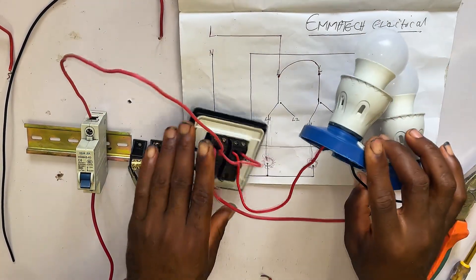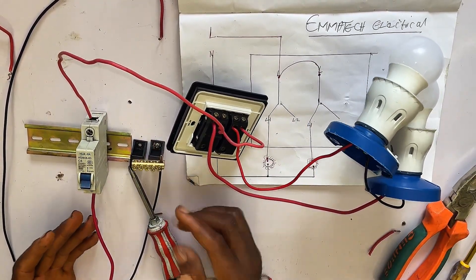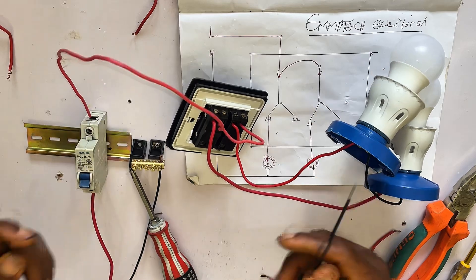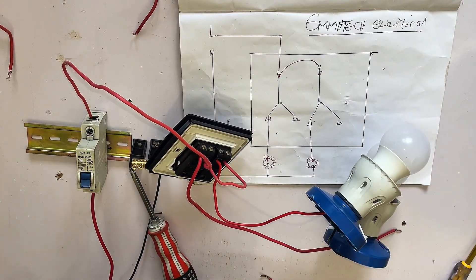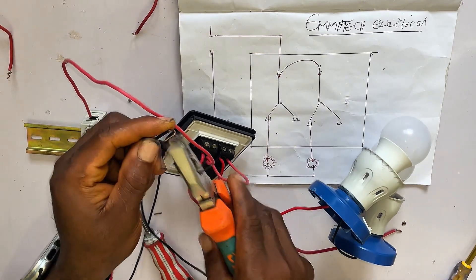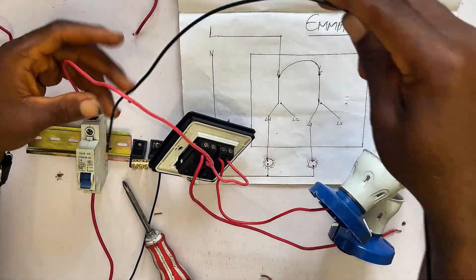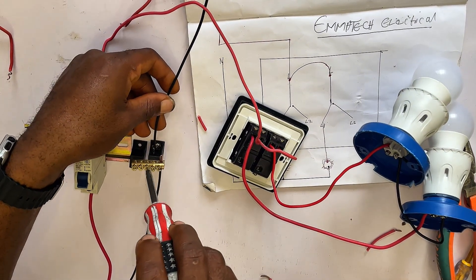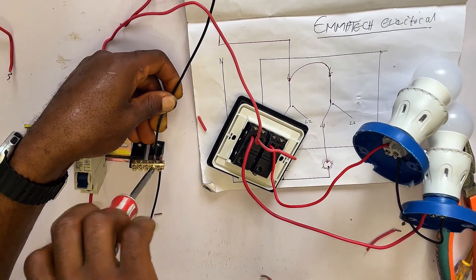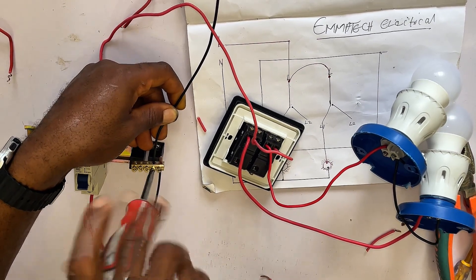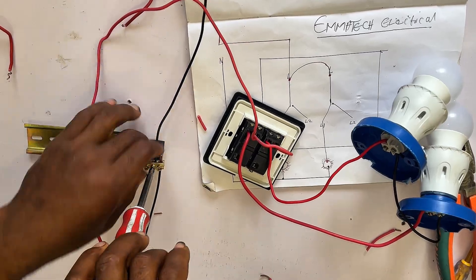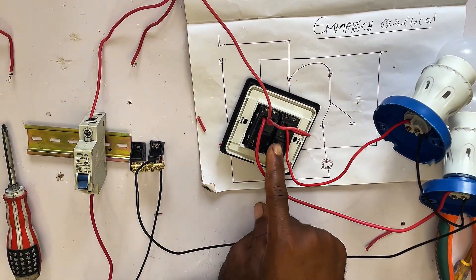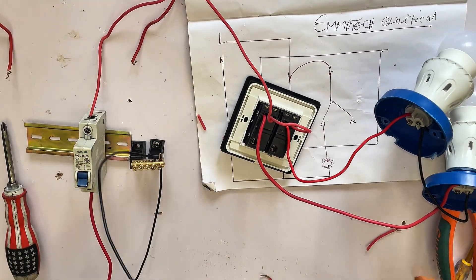Now what remains is our neutral wire. We are going to connect our neutral from the neutral link directly to our bulbs. You can see this is our neutral connector here. Pick a black wire like this and connect it to the neutral. Remember — you don't connect the neutral to your switch; the neutral goes directly to your bulb.